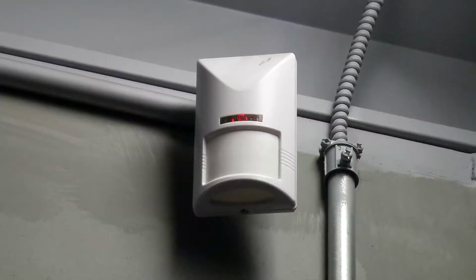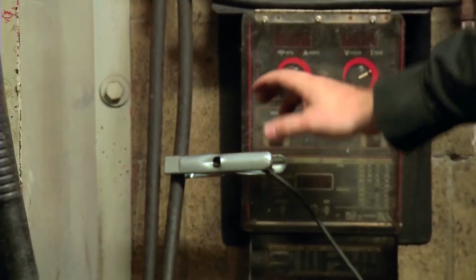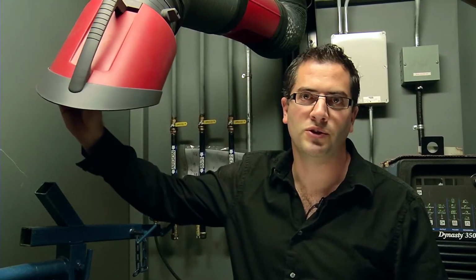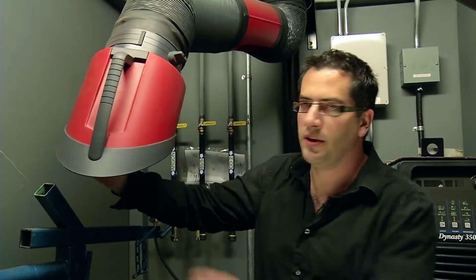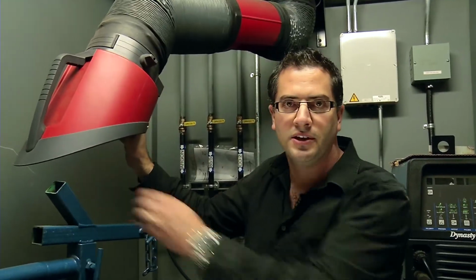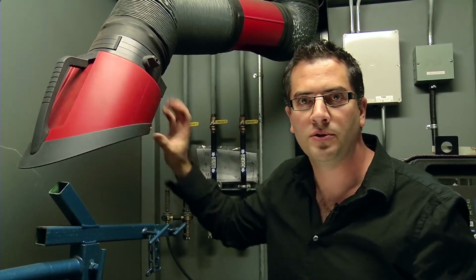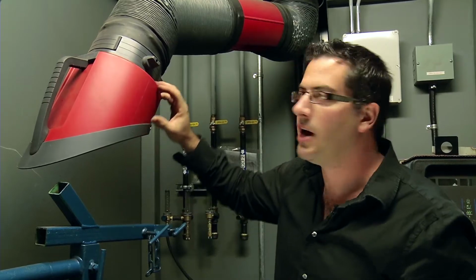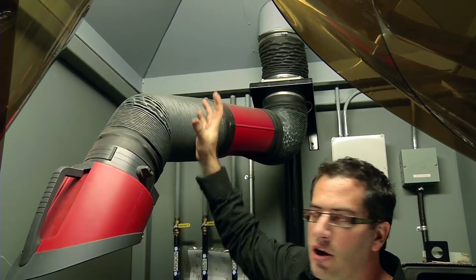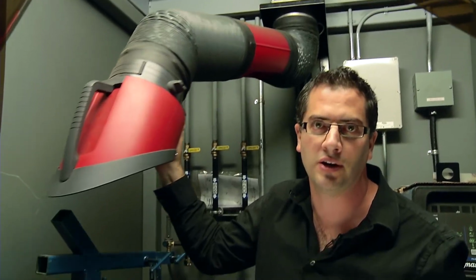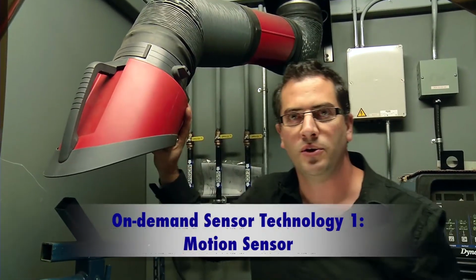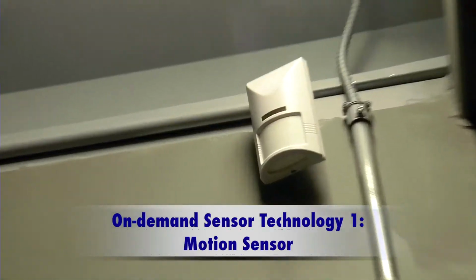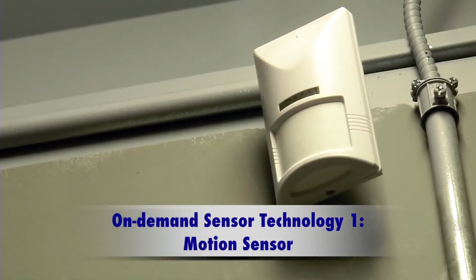Each booth is individually controlled by either a motion sensor or an arc sensor. The snorkel is our main source capture. We can move this where the welding is being done between 6 to 8 inches away to extract the fumes that are being created. The secondary source capture is this exhaust hood up here. So there's less CFM running through here, but there's about 600 running through the exhaust hoods. So this is only activated when you're in the booth moving around, because we have a motion sensor up here in the back corner.